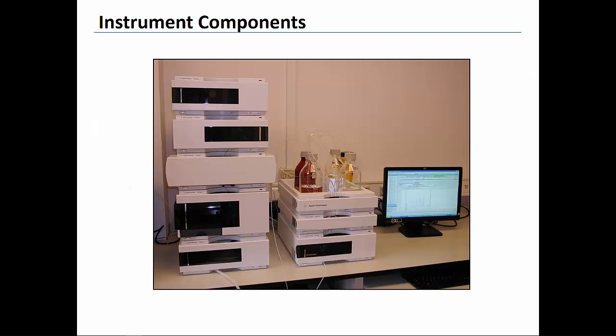In order to save bench space, modern HPLC instruments are configured with stackable components. This picture illustrates a typical HPLC system manufactured by Agilent. The solvent bottles are placed in a secondary container, which rests on top of the pump. The stack of components includes an auto sampler where sample vials are housed, a column compartment, and one or more detectors.